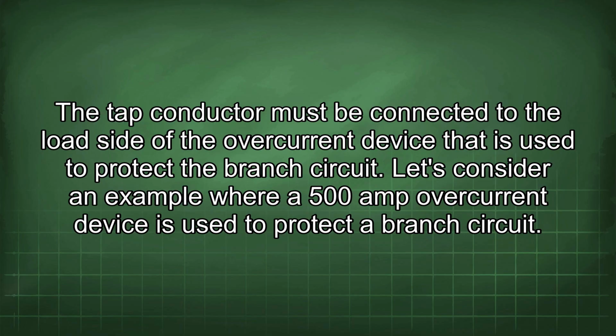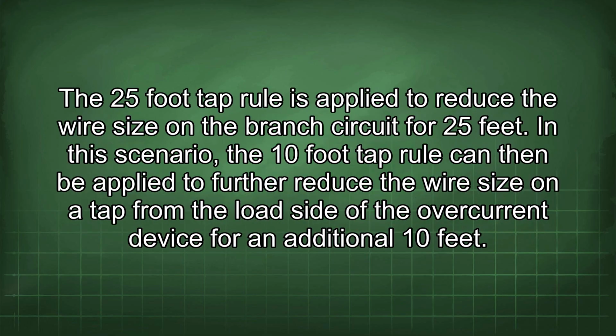The tap conductor must be connected to the load side of the overcurrent device that is used to protect the branch circuit. Let's consider an example where a 500 amp overcurrent device is used to protect a branch circuit. The 25-foot tap rule is applied to reduce the wire size in the branch circuit for 25 feet. In this scenario, the 10-foot tap rule can then be applied to further reduce the wire size on a tap from the load side of the overcurrent device for an additional 10 feet.